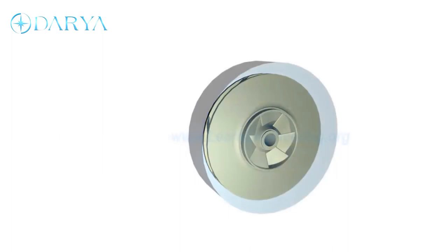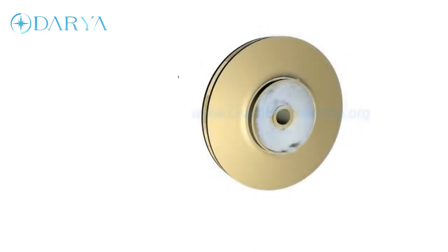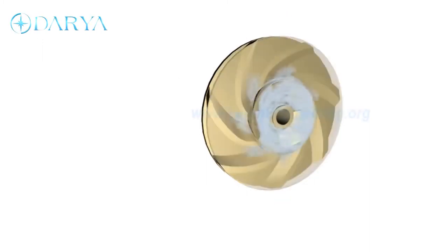When the impeller is made to rotate, it makes the fluid surrounding it also rotate. This imparts centrifugal force to water particles and the water moves radially out. Since rotational mechanical energy is transferred to the fluid, at discharge sides of impeller, both pressure and kinetic energy of water will rise.